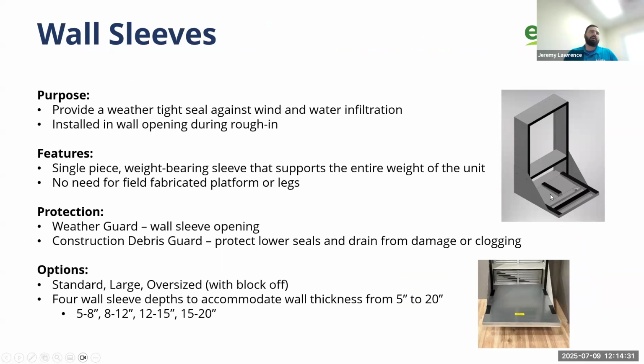So as I said, the sleeve supports the weight of the unit. It is one piece and shipped as one piece. There are no legs because these triangle supports are in place to hold the weight of the unit. There is a side access sleeve. If you needed to install this unit from the side, there's a side version that doesn't have these triangle supports, and there is a separate support that comes underneath and cradles the unit. However, more considerations need to be taken if the side install is preferred, because we do need to make it known that the cradle support needs something to secure to, right? So if we're doing a concrete structure with steel studs, steel studs aren't going to be able to take that weight. So more often we would try to find ways to use the rear access sleeves, which, as shown, and otherwise, you would need to put some blocking in behind the wall that would allow for that unit to be supported.